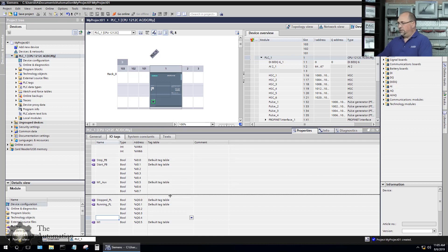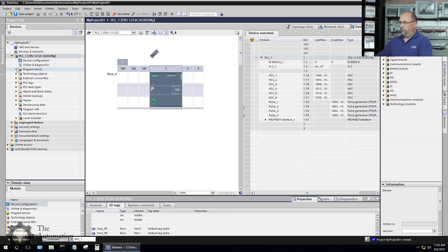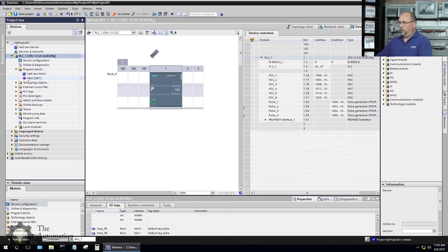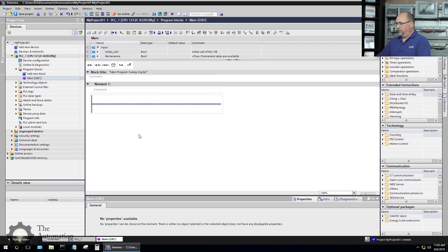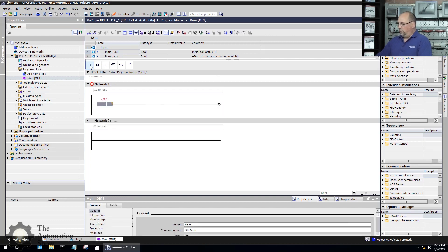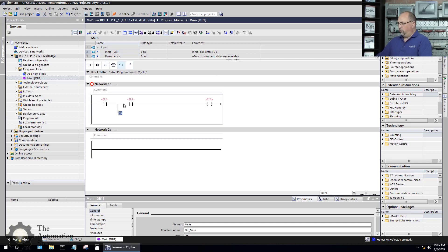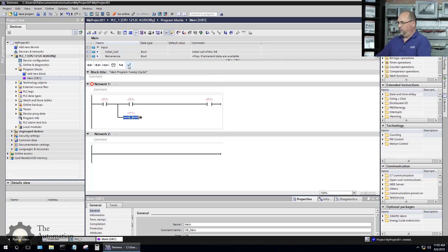So let's go ahead and bring this down a little bit here. We'll go over to program blocks and we'll open up our main OB1 program block. OK, we'll select the first rung here. So I'm going to have stop, start, motor. But I also need a branch. So I want to insert a branch around my start button because I'm using a momentary start button. And I will put in another contact there for the auxiliary and I'll close that branch. Excellent.